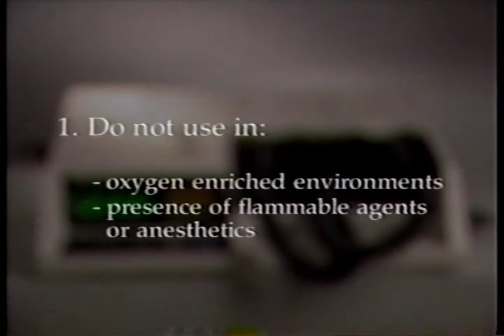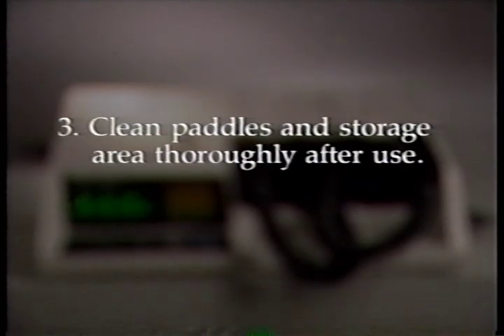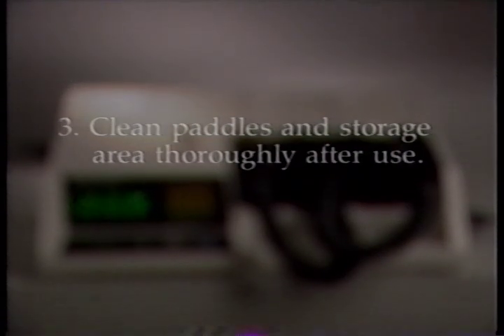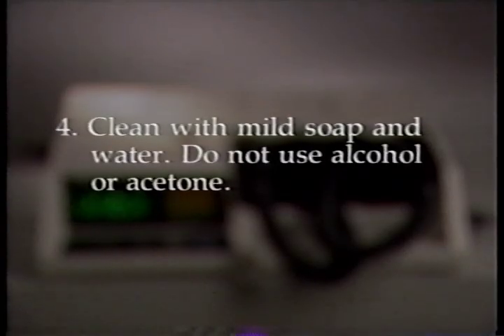This device should not be used in oxygen-enriched environments or in the presence of flammable agents or anesthetics. Such use presents a possible fire or explosion hazard. Do not immerse the device in water or other fluids. Doing so may damage the device and may cause a fire or shock hazard. Clean the defibrillator paddles thoroughly after each use. Buildup of gel could produce a shock hazard to the user. Clean the paddle storage area anytime it's soiled with gel. Clean the LIFEPAK 10 and its accessories with mild soap and water. Do not use alcohol or acetone.